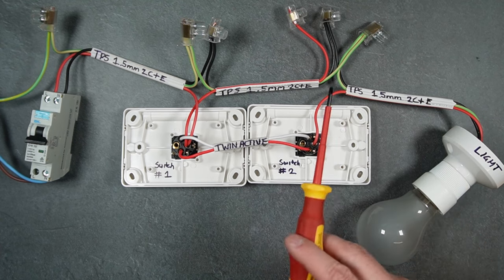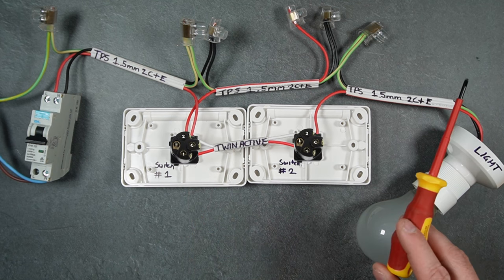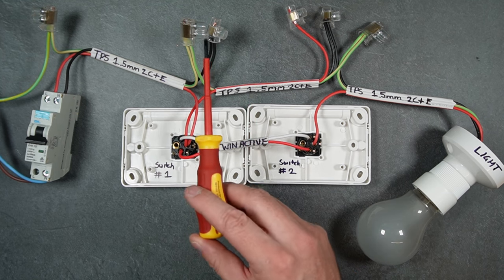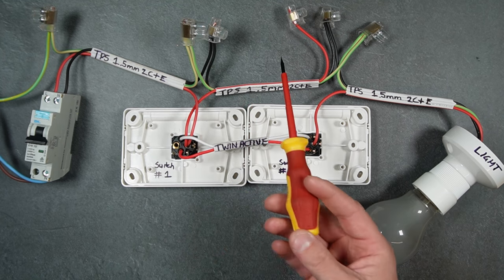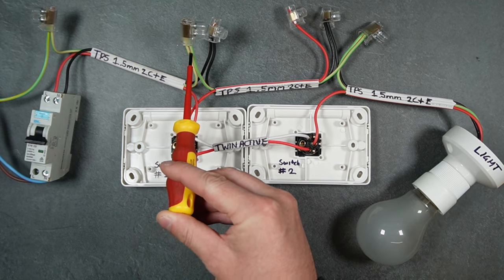You might find the neutrals in the loop-in terminals, which is fine, but I do prefer to join the neutrals in a connector because it provides a much better connection. The earth will either be in a connector or soldered and taped back to the TPS - that's also normal.